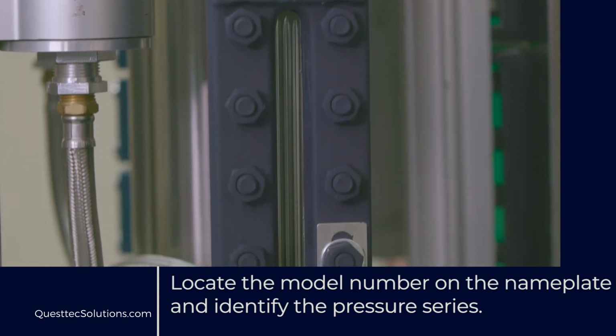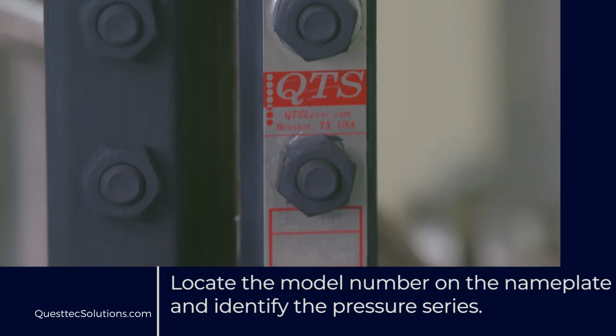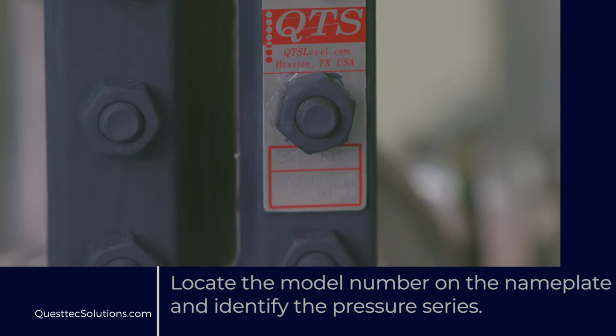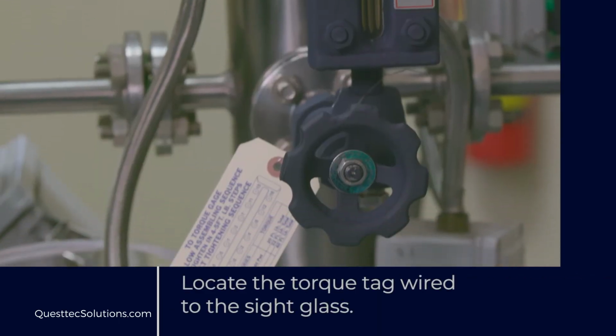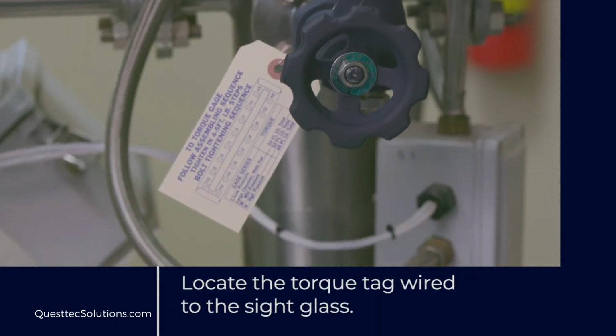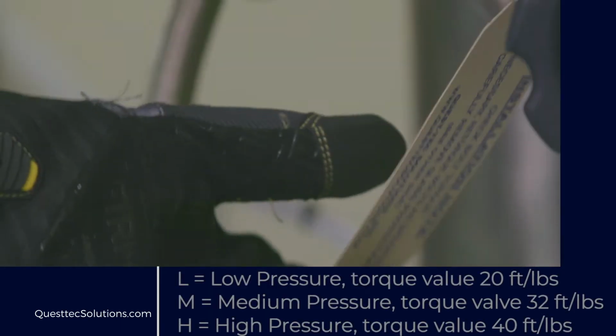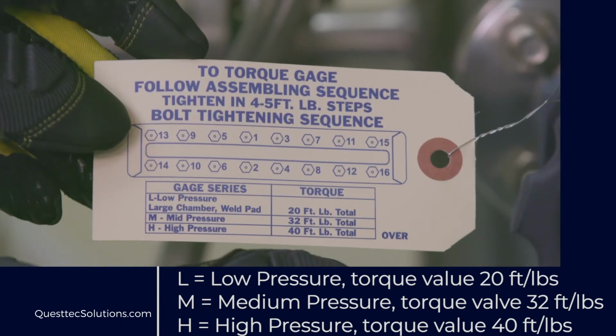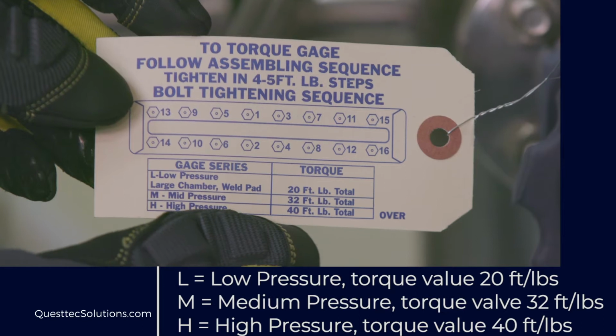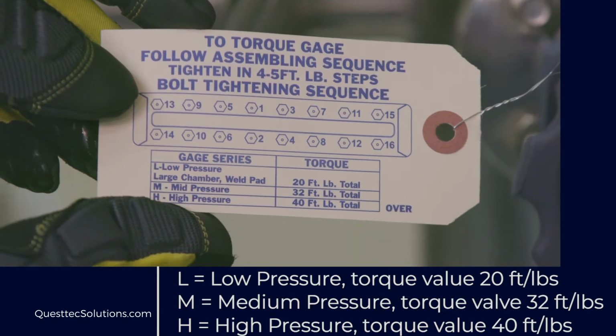Identify the pressure series of the sight glass by locating the model number on the nameplate. Locate the torque tag wired to the sight glass. L equals low pressure, torque value 20 foot-pounds. M equals medium pressure, torque value 32 foot-pounds. H equals high pressure, torque value 40 foot-pounds.